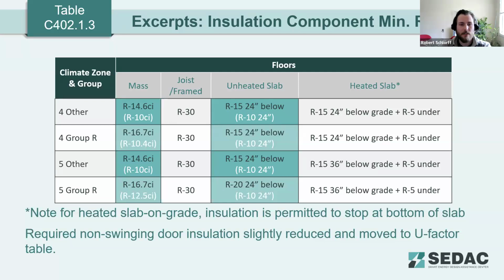That's not exactly where we want it to be. We want it to be heating the floor and not going anywhere else. So the interpretation of that note there is that heated slabs should be fully wrapped. If insulation is broken by a stem wall on a heated slab, say the foundation requires that the stem wall breaks that insulation at the perimeter of the slab, then the perimeter insulation should extend down the full depth as stated within the code, so 24 inches below.